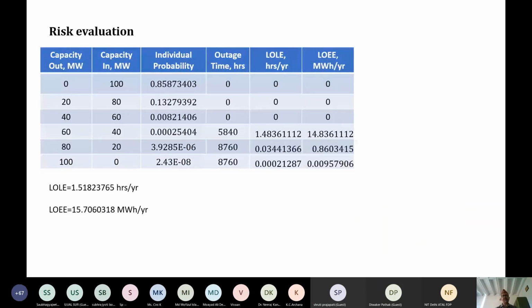And then risk evaluation. What we do is we put the load model and the generation model together, or we cumulate them together, and then we find out, for example, when capacity outage was 0, the whole 100 megawatt is available with this probability, and outage time is 0 hours, LOLE is 0, and loss of energy expectation is also 0.